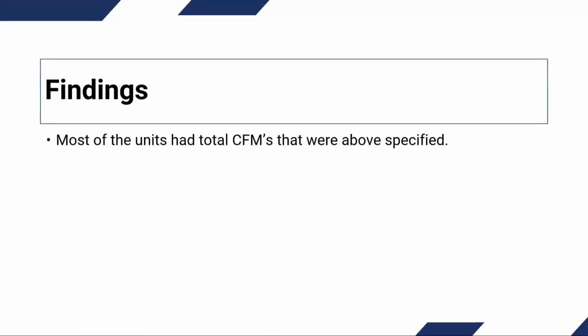What we found at this particular project, the majority of the units that we measured had CFMs that were above the specified CFM, which is always a problem because we cannot do the latent capacity at a higher CFM. So almost all the units were more than 10% above specified capacity. Even those that were within specified capacity were at the higher end. They were 8 to 10% above specified CFM on the units.